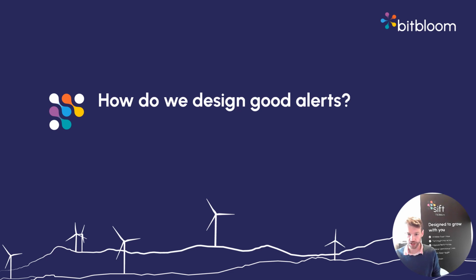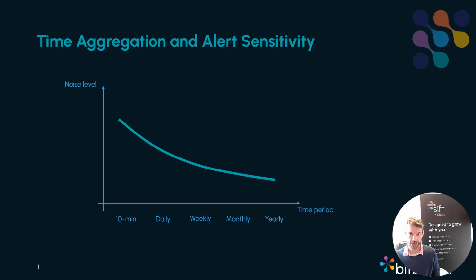So how do we design good alerts? Well, this in many ways is the key point of why we do that condensing of the data. If we just stick to working with 10-minute data, or whatever raw frequency it may come in, then the noise level on that tends to be quite high. But as we aggregate that over longer time periods, then these noise levels decrease.